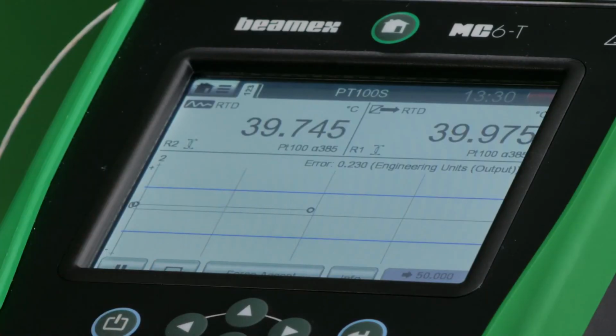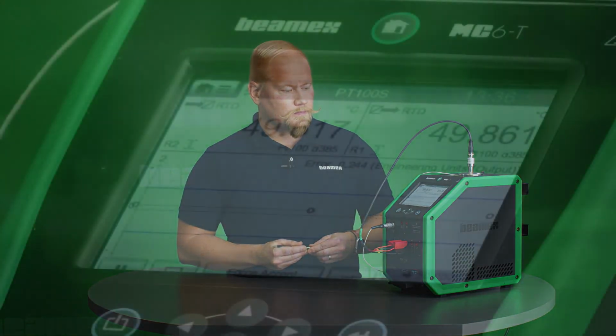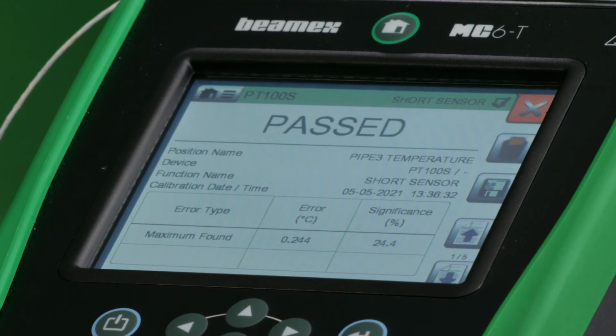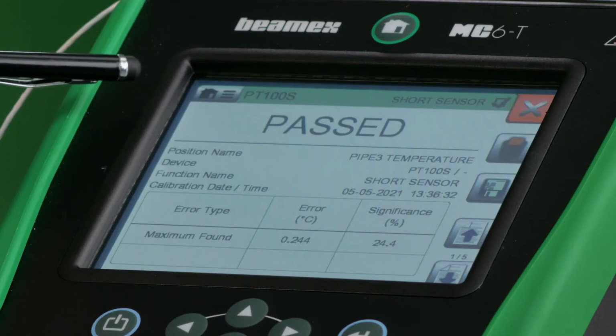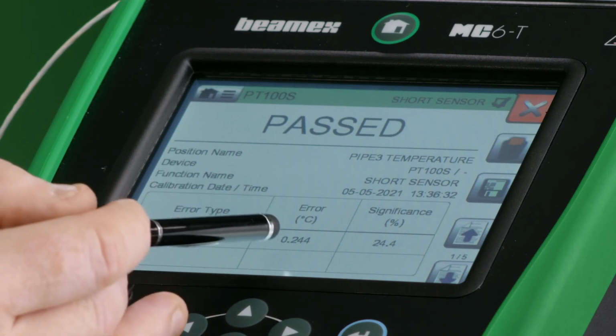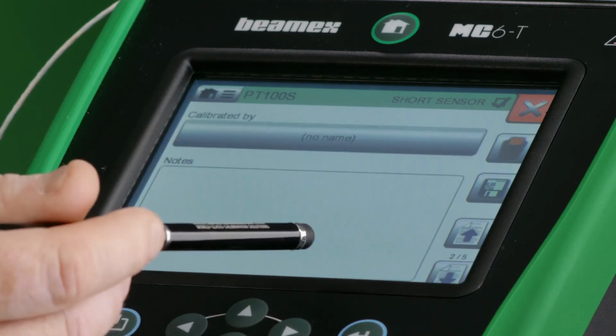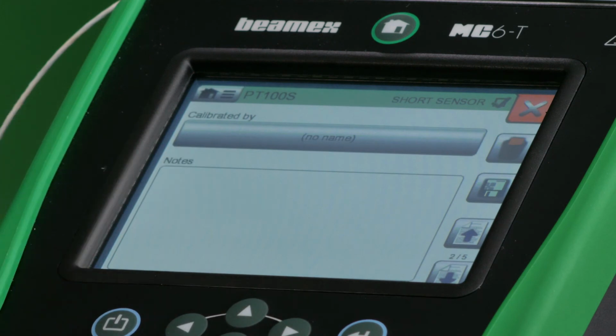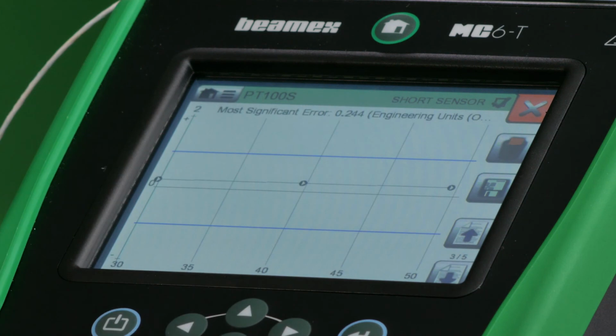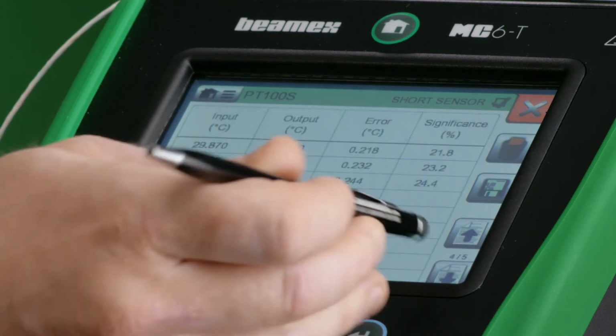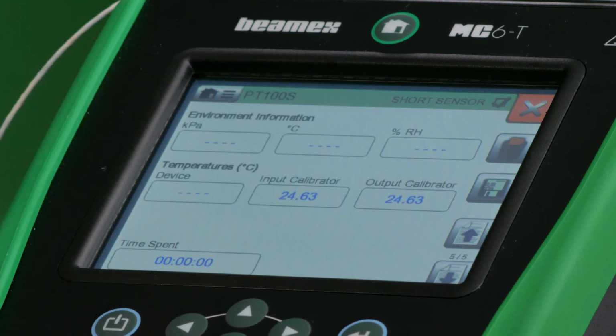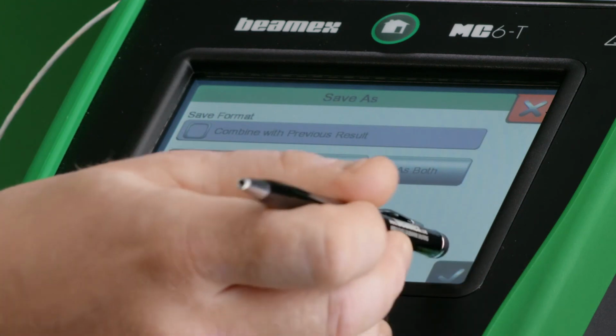The second set point is now reached. We see that it has drawn a green, very nice line. And it has now given my third and final set point, which is 50 degrees Celsius. We have now reached the last set point for this calibration. I see that I have a passed result. I can also see my error and its significance. I can put a note here. See my results in a graphical view and also in numerical view. And if I like, I could also put some environmental information here. I'm going to save it as found.